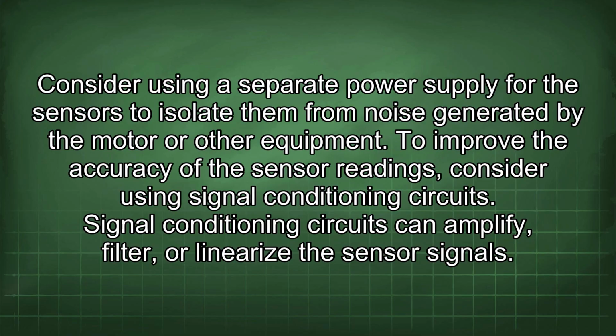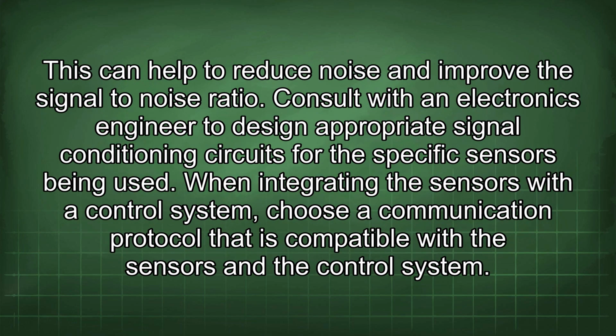Consider using a separate power supply for the sensors to isolate them from noise generated by the motor or other equipment. To improve the accuracy of the sensor readings, consider using signal conditioning circuits. Signal conditioning circuits can amplify, filter, or linearize the sensor signals. This can help to reduce noise and improve the signal-to-noise ratio. Consult with an electronics engineer to design appropriate signal conditioning circuits for the specific sensors being used.